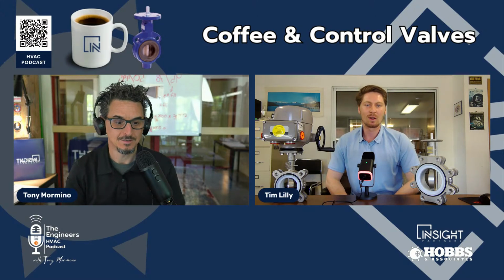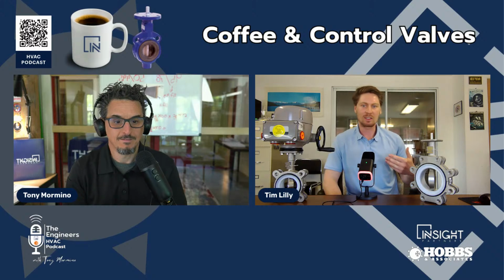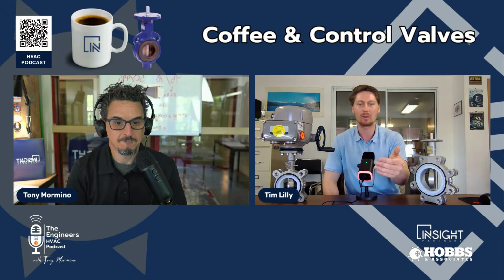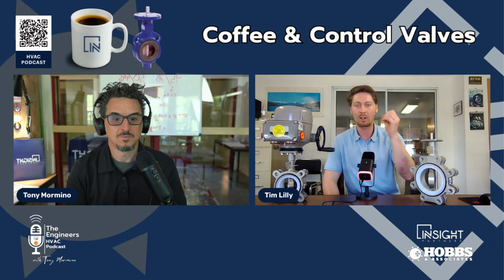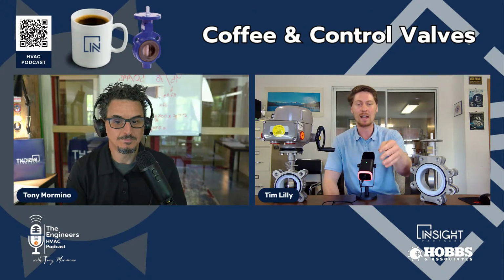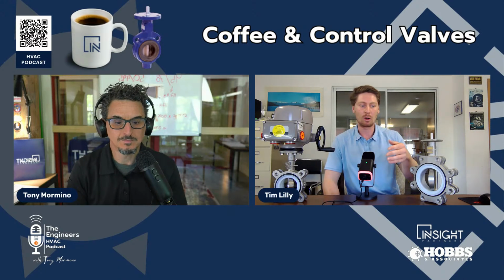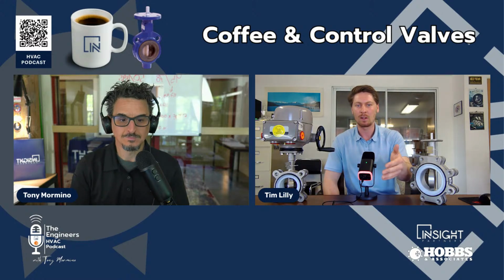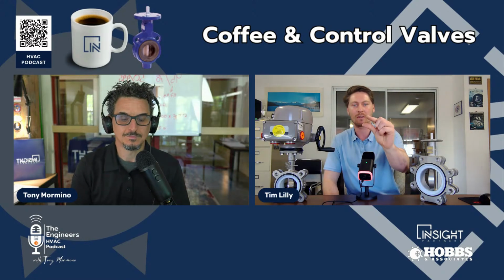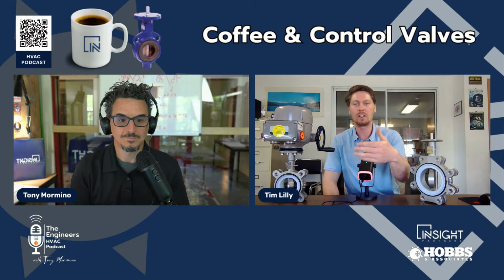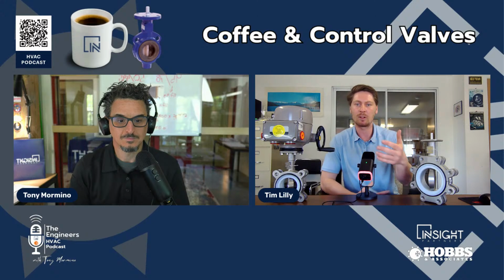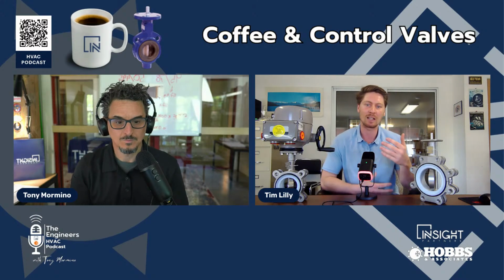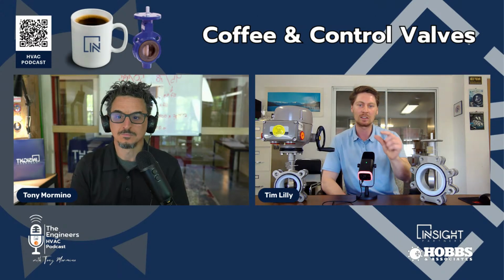Okay, gotcha. What happens is, with a control valve, what you're trying to do is eat some of that energy. You have too much energy going through your pipe. You need to knock it down. And how you knock it down is important. If you use a characterized ball where you have that slit, your CVs are a little bit lower, and you might have to go down a size, you might have to go up a size because they control within a narrow range.